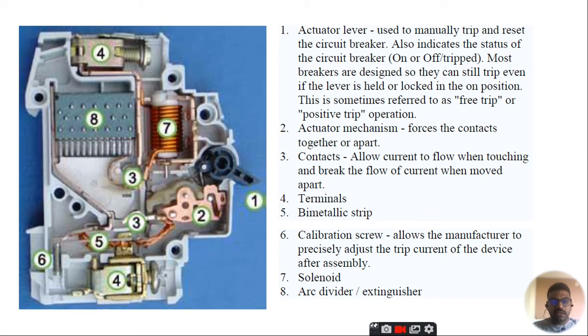We have the calibration screw - most important, it allows the manufacturer to precisely adjust the trip current of the device. Then we have the solenoid, arc divider, and extinguisher. The actuator lever is used to manually trip and reset the circuit breaker.